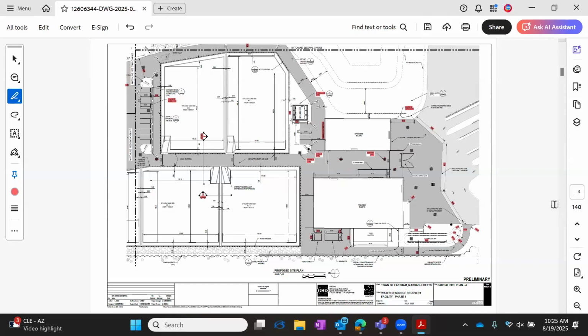We've really only got one building that has fire protection, and that's the treatment building. It has an H occupancy based on maximum allowable quantities being exceeded for corrosive fluids, which triggers our sprinkler system. So the treatment building has a sprinkler system and a fire alarm system monitoring it, with notification and manual pull stations. I believe we only have a detector at the panel.